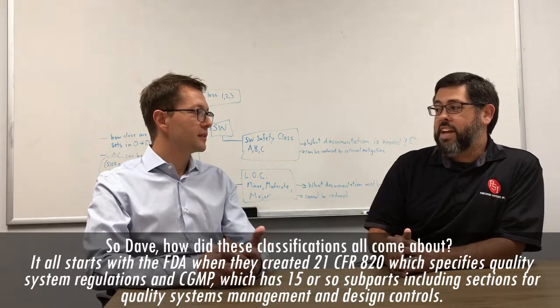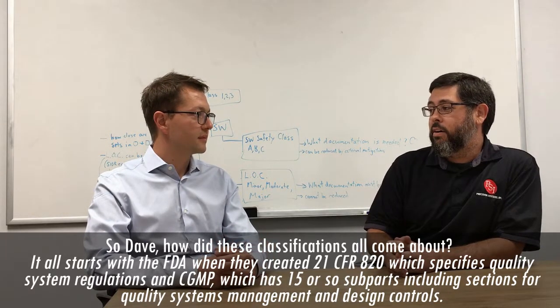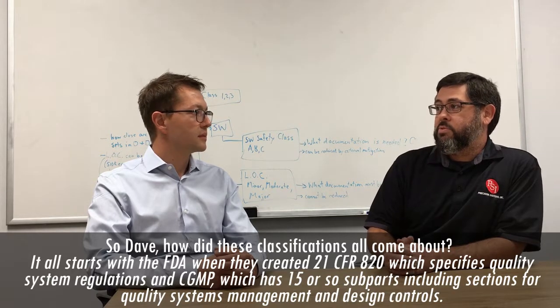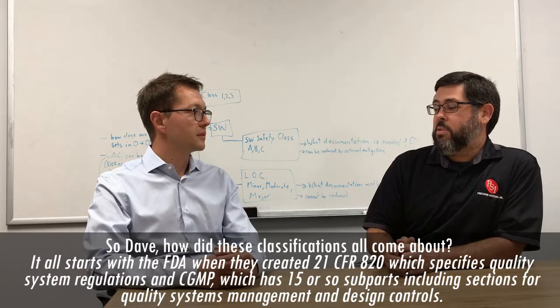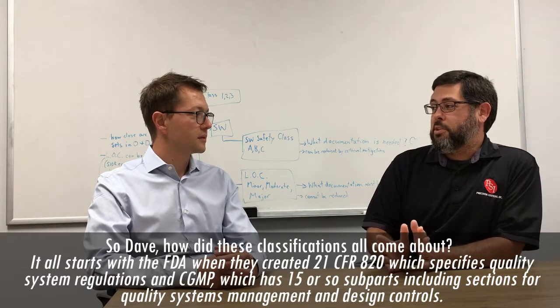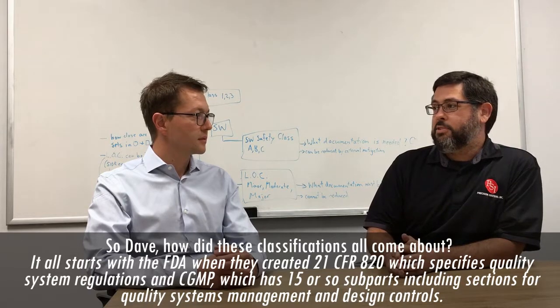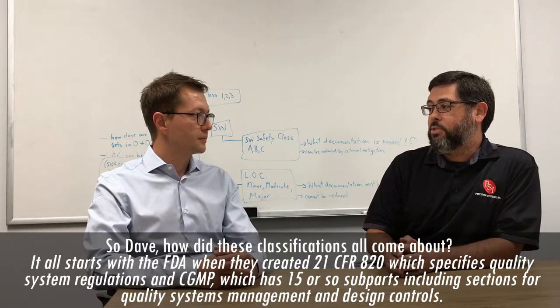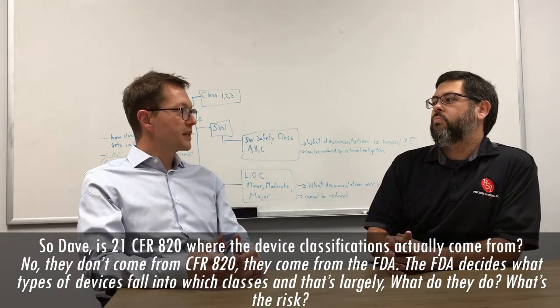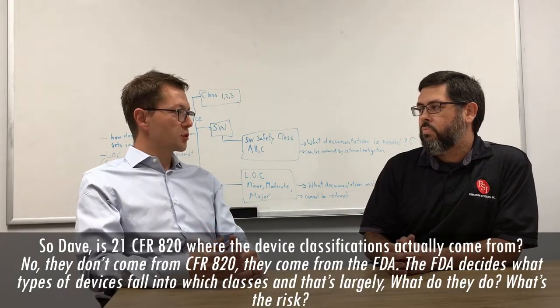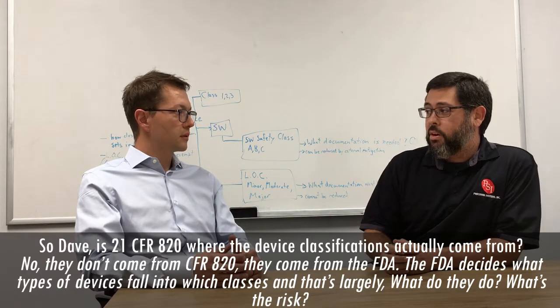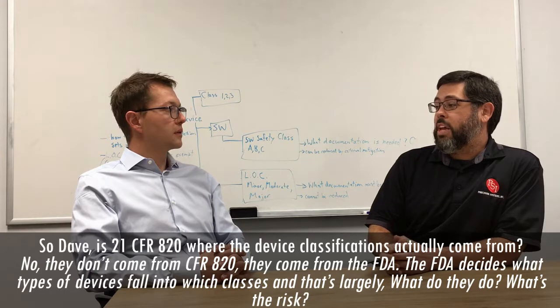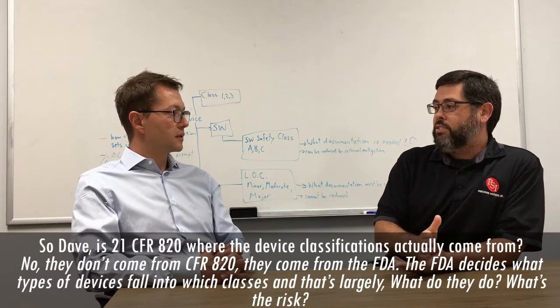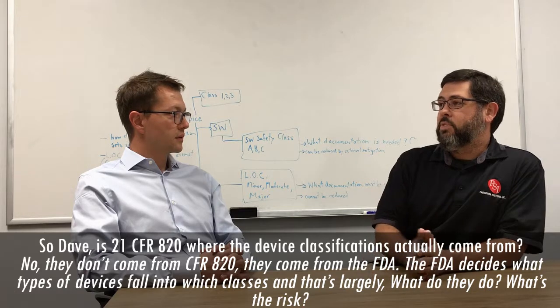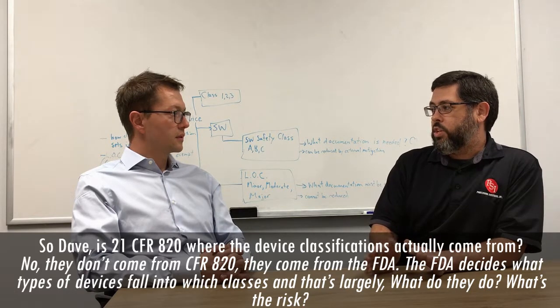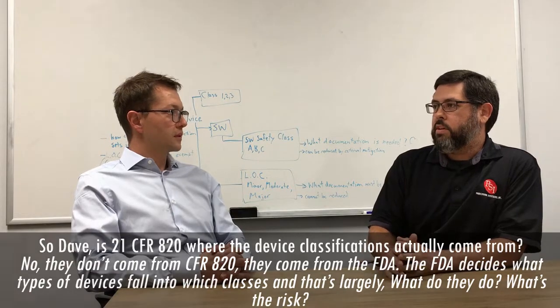Well, it all starts with the FDA when they created 21 CFR 820, which specifies quality system regulations and CGMP, which has 15 or so subparts, including sections for quality systems management and design controls. So Dave, is 21 CFR 820 where the device classifications actually come from? No, they don't come from CFR 820. They come from the FDA. The FDA decides what types of devices fall into which classes. And that's largely what do they do? What's the risk? That's how they determine it.